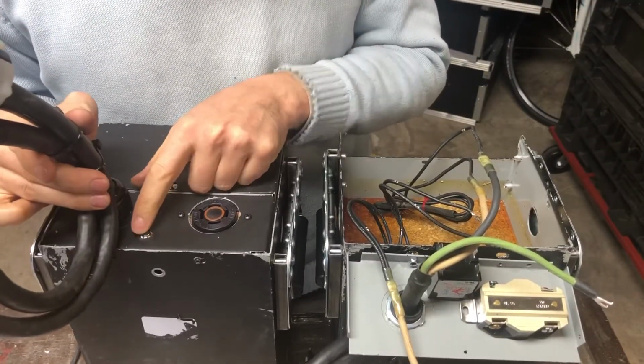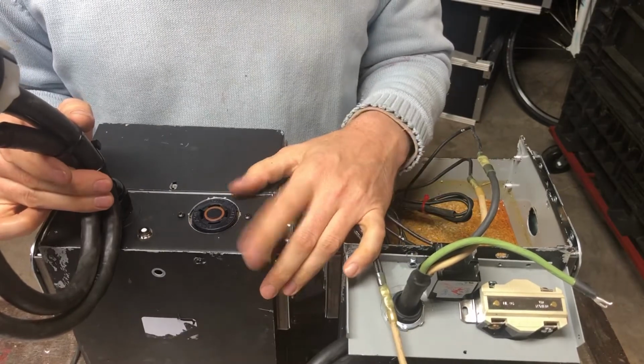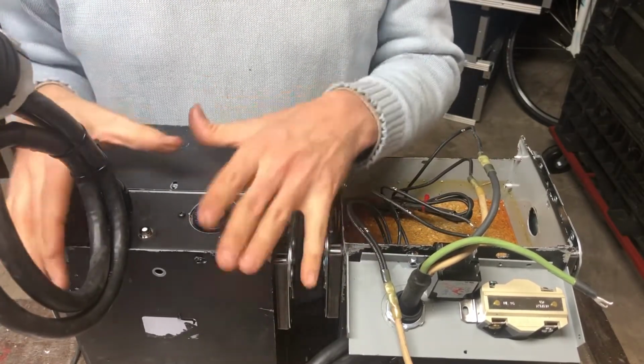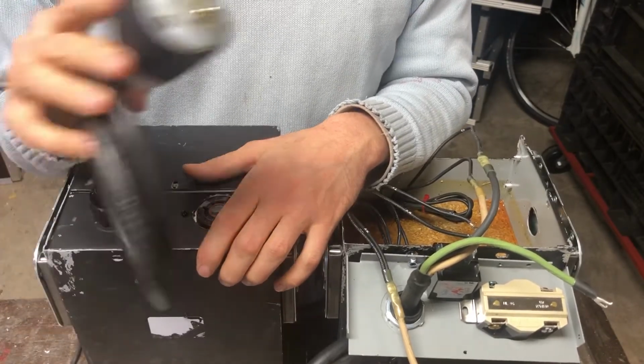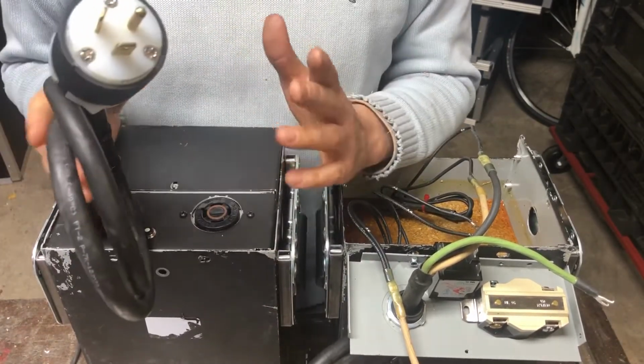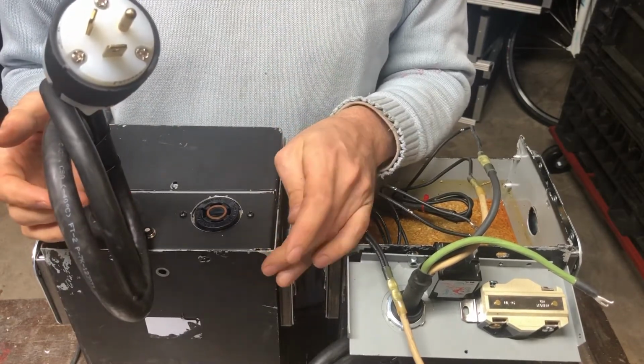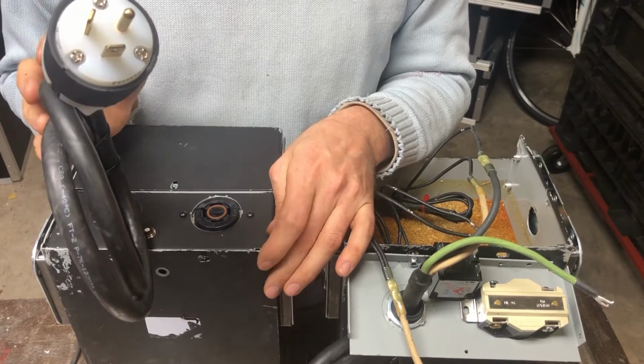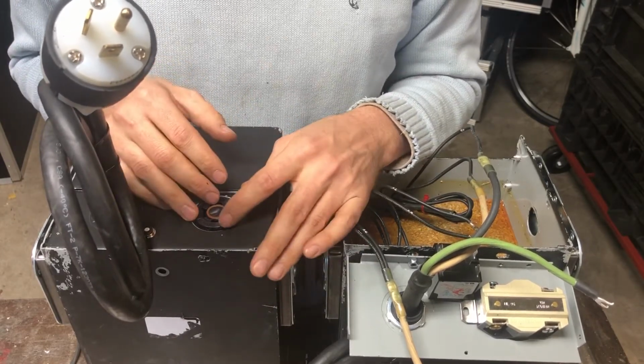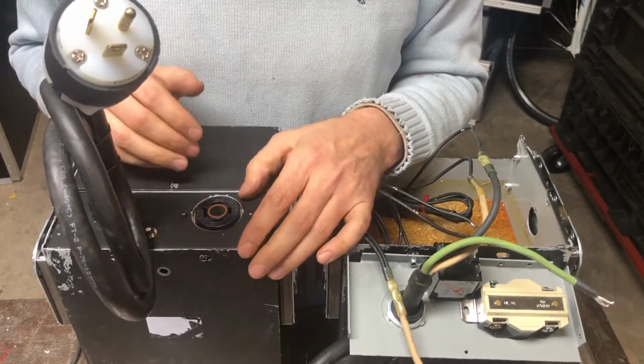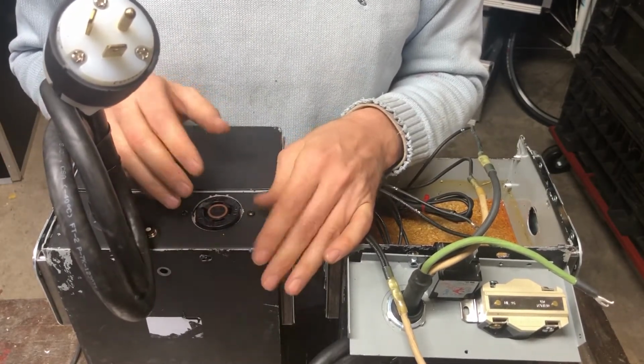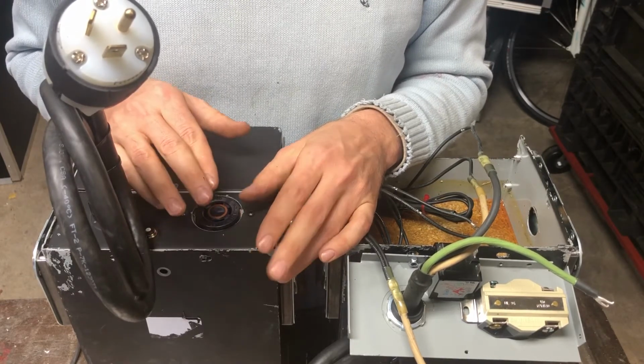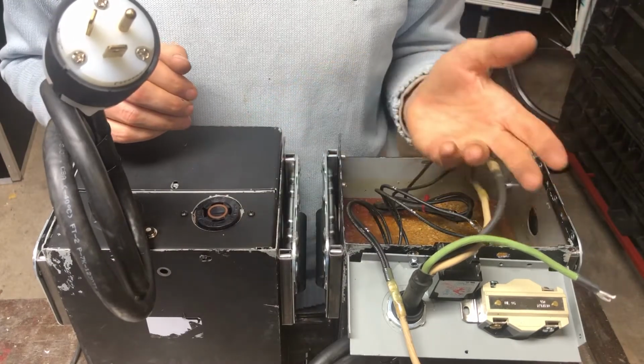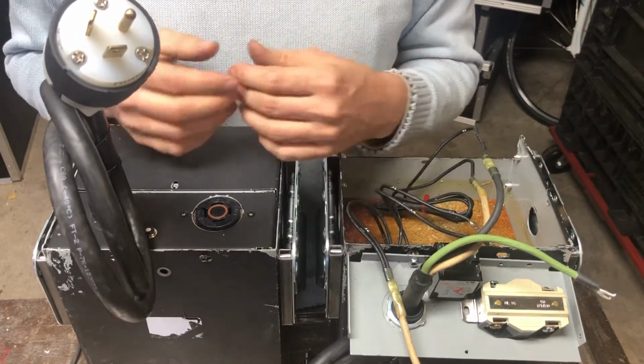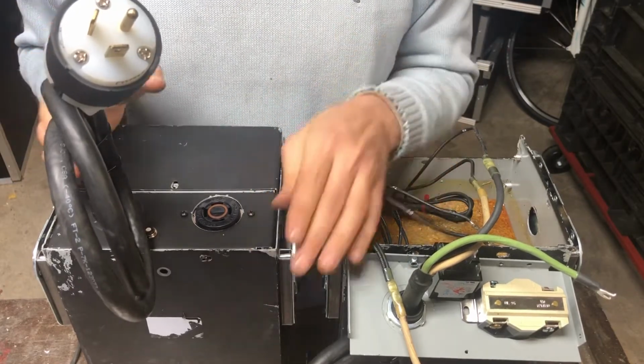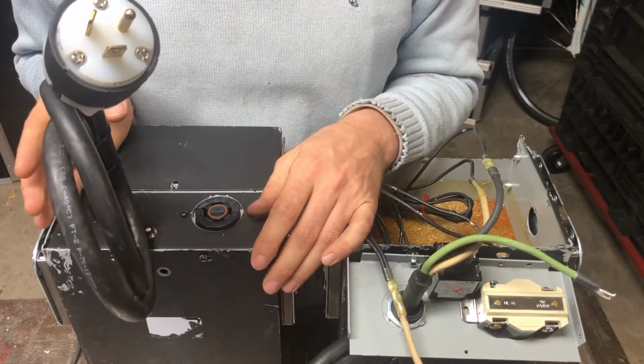Our circuit breaker is here, so it pops out if it gets overloaded, and it's a 5 kVA transformer. So our input is 20 amps, 277 again, but we're only going to use 80% of that. So 80% of that input potential gives us really close to 15 amps, 14 and a lot, so very close to 15 amps per phase available. We're going to use the 2 phases with an L1420 extension and then a breakout, like a little fan that breaks out to single 515 or Edison connectors, and we're going to use that to power the equipment we have to run.